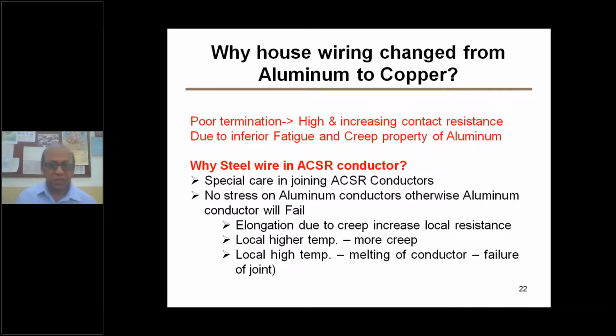Now let's come to why steel wire is used in ACSR conductors. I gave this example while delivering a lecture in Lucknow at a seminar. When I explained creep behavior, an engineer told me he now understood why ACSR conductor joints are failing. Joints only fail when there is stress on the aluminum wires; so long as the stress is on the steel wire, there is no question of failure. As soon as the connection is bad and stress comes onto the aluminum wire, then with time, maybe one month, maybe three months, depending on stress and temperature conditions, it's bound to fail. We can't stop it, so we must take care in joining ACSR conductors.